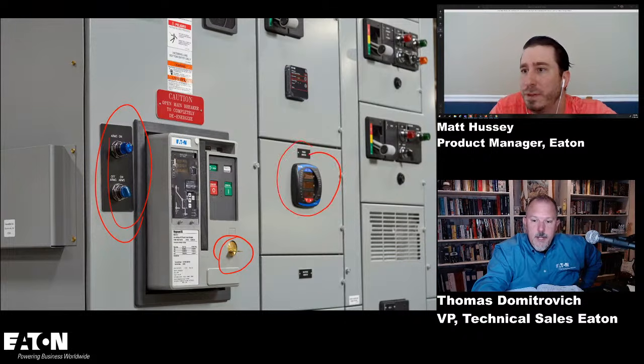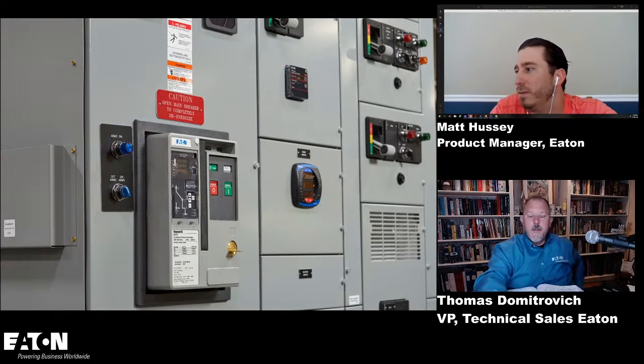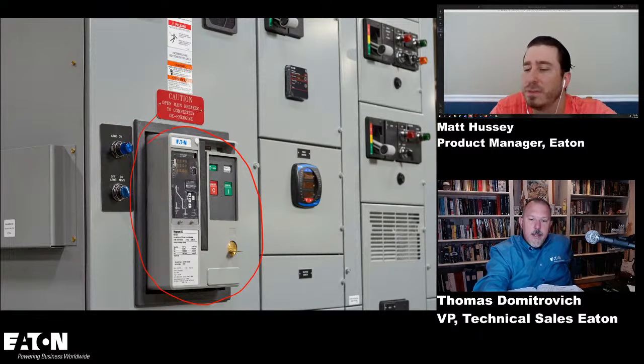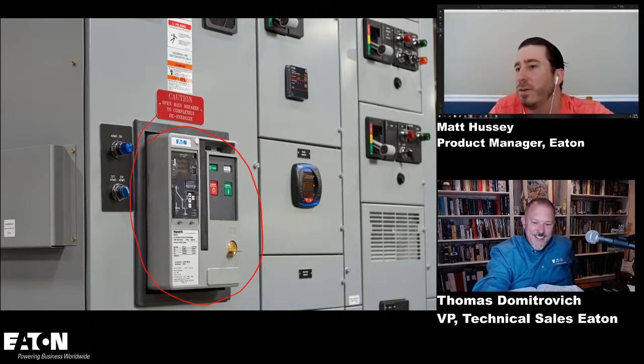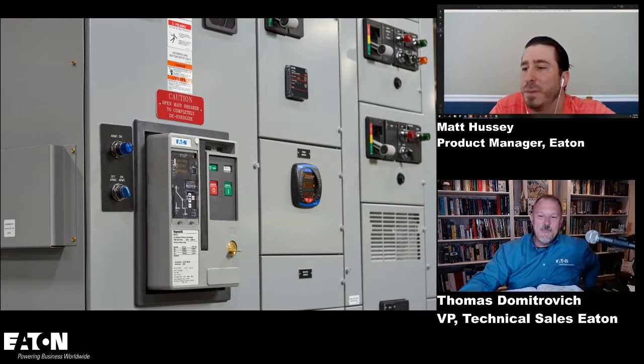We got some meters. And what's that there? Is that surge? Yep, that's your surge protective device. Surge protective device, all right. And that's important around motors too. Why couldn't you fit this breaker all the way in? How come it's sticking out like that? That's a draw out construction. All right, yeah, that's probably it racked out. Just pulling your leg.